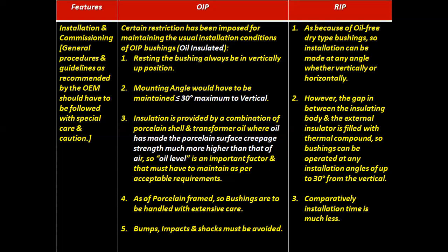And in the case of RIP bushings, because they are oil-free dry type bushings, installation can be made at any angle, whether vertically or horizontally. However, the gap between the insulating body and the external insulator is filled with thermal compound, so bushings can be operated at any installation angle of up to 30 degrees from the vertical. Comparatively, installation time is much less as compared to OIP bushings.